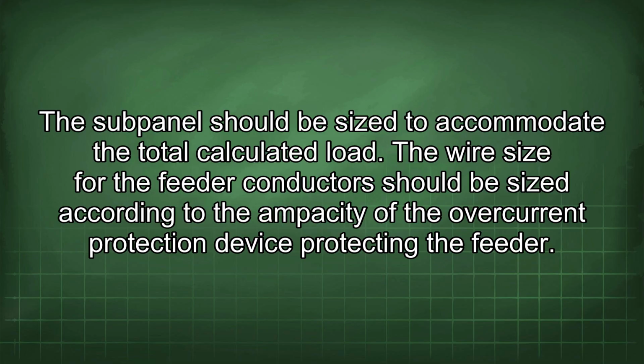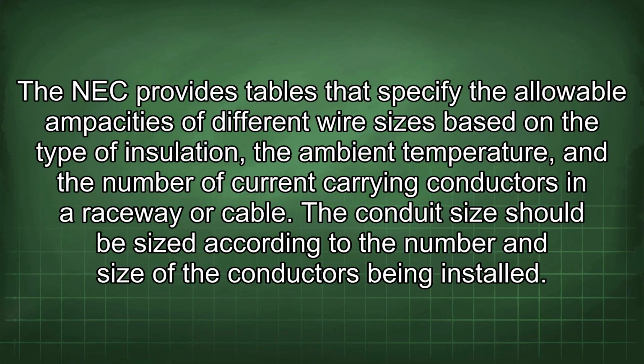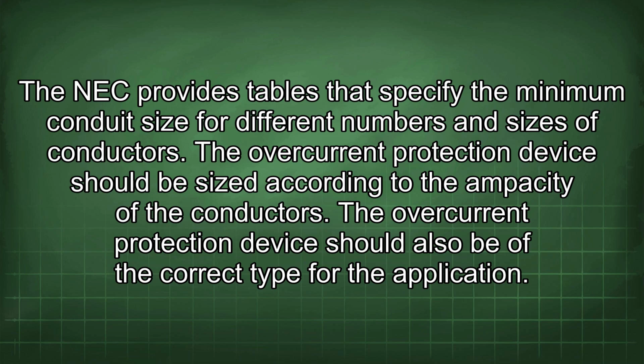The wire size for the feeder conductors should be sized according to the ampacity of the overcurrent protection device protecting the feeder. The NEC provides tables that specify the allowable ampacities of different wire sizes based on the type of insulation, the ambient temperature, and the number of current carrying conductors in a raceway or cable. The conduit size should be sized according to the number and size of the conductors being installed. The NEC provides tables that specify the minimum conduit size for different numbers and sizes of conductors.